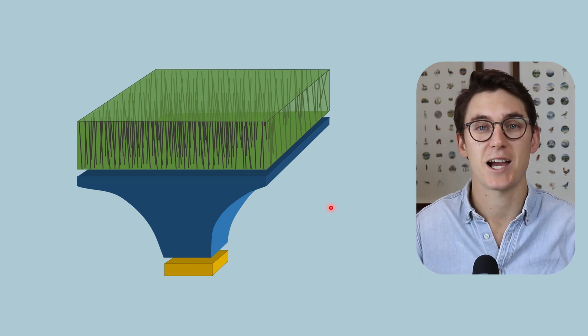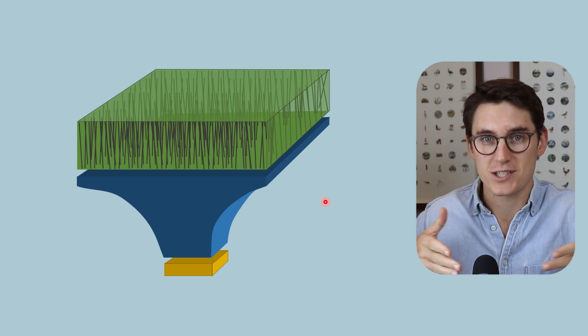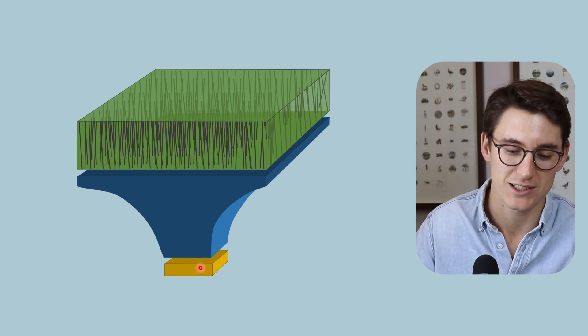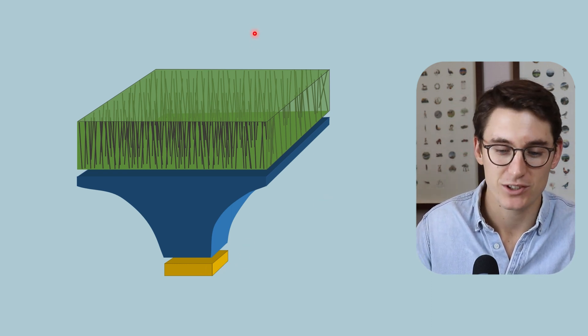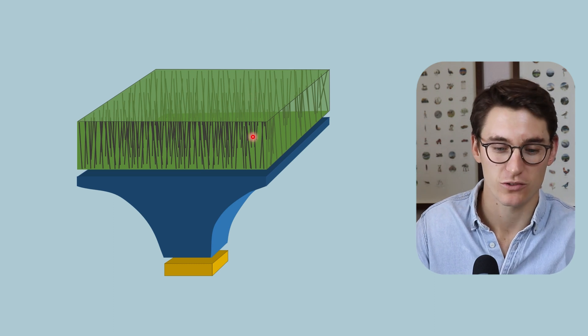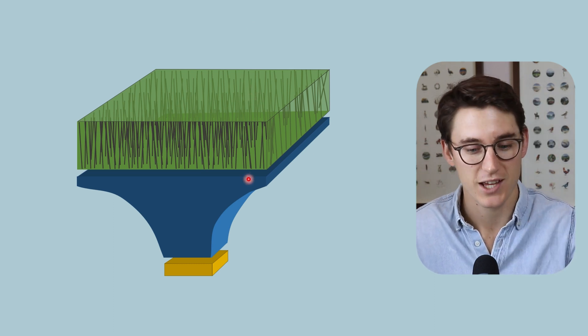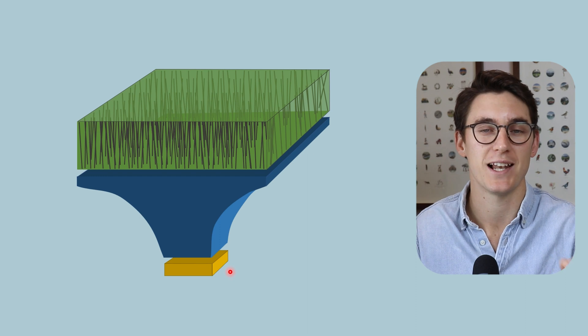The second type of coupling device is a lens that can focus that light down onto our CCD chip. Now we are taking X-ray photons, converting them to light photons, and then converting them into electrons.